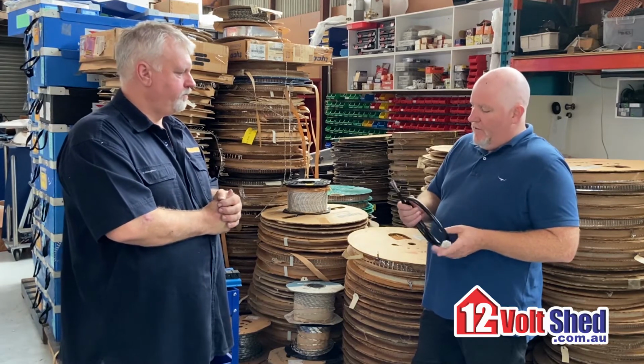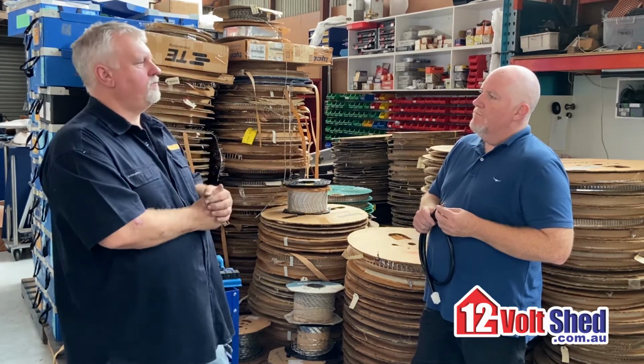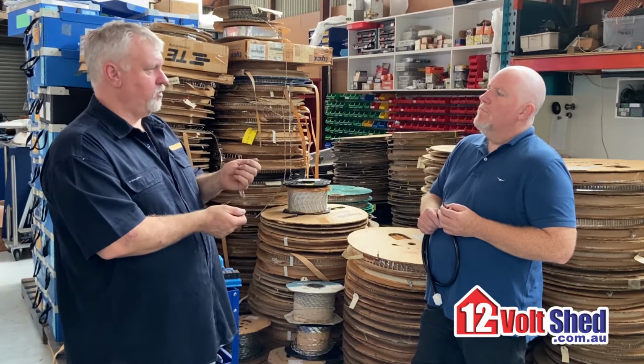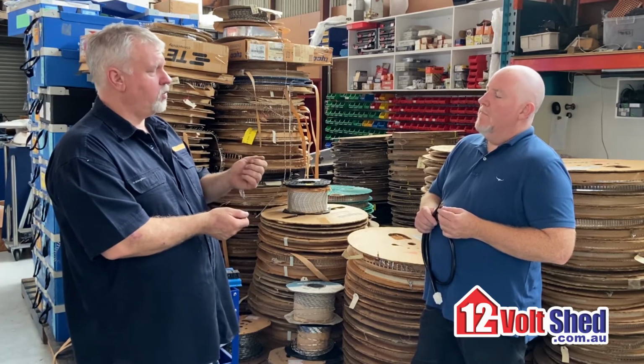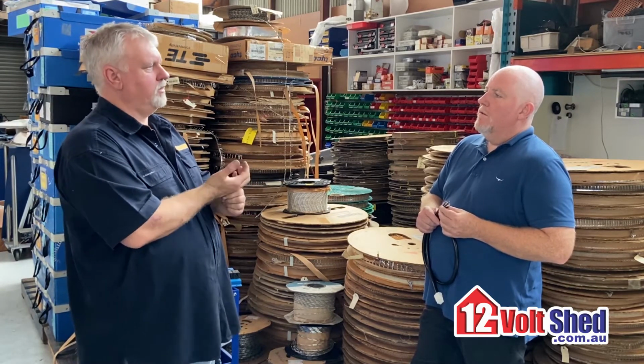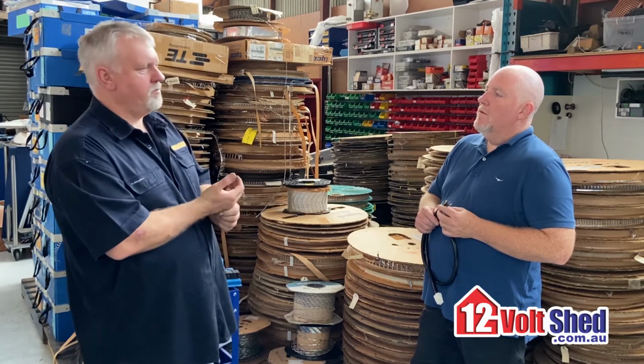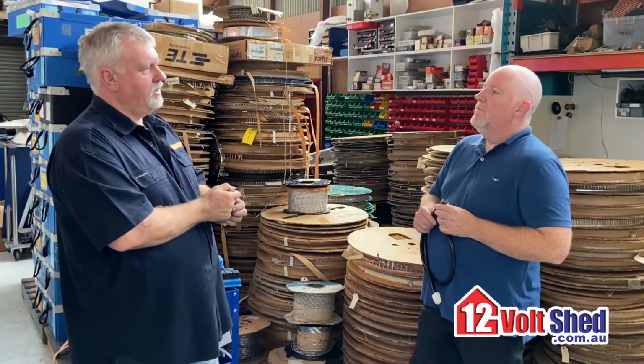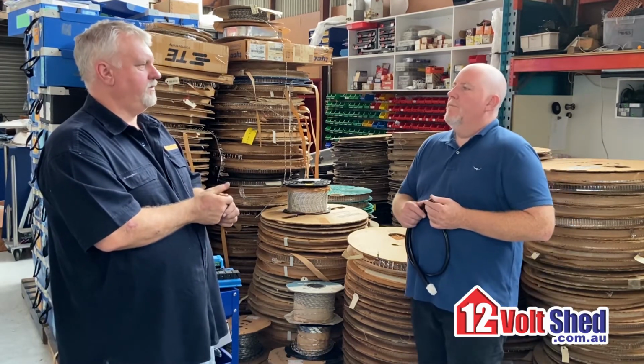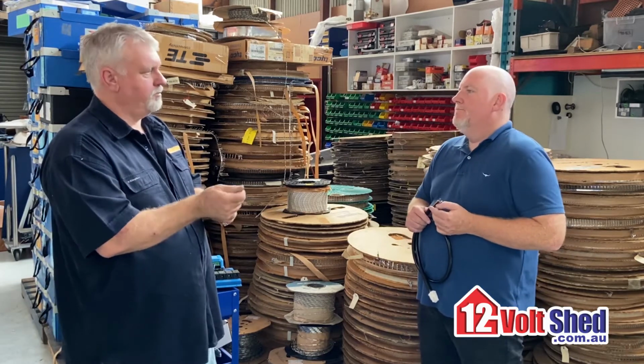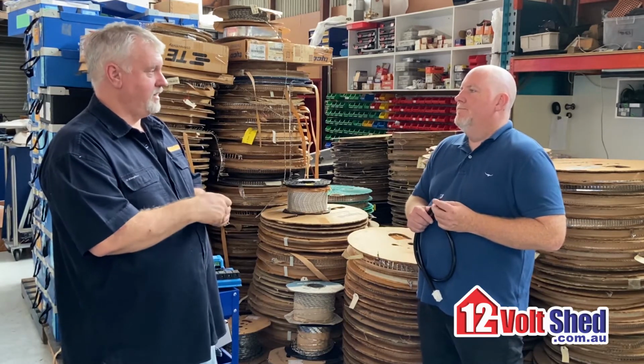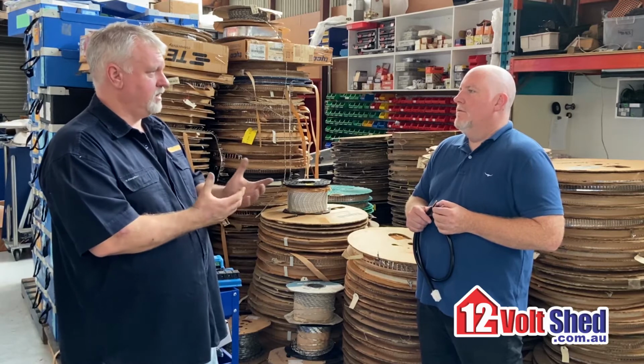Well, that's a really fantastic tip. And when you go and crimp that, if you strip a wire and find they're all black, which you'll find on a lot of boats or old wire, and crimp a terminal, you instantly get a high resistance joint, because you're actually crimping against all the tarnish. If you've got to use it, you sit there for a period of time until you get rid of the black tarnish off it, and if you can, solder it, because you can get a decent connection.